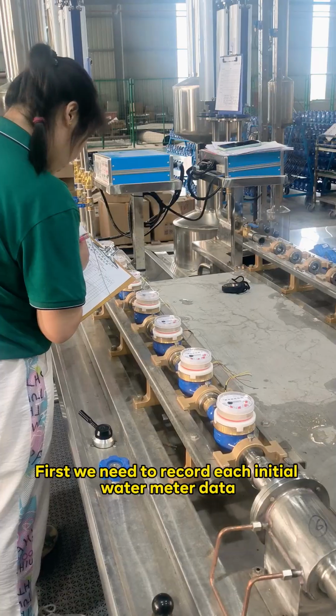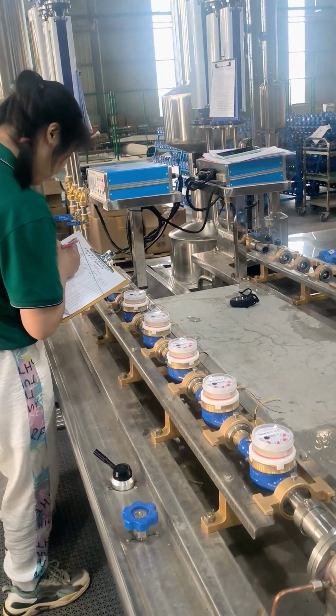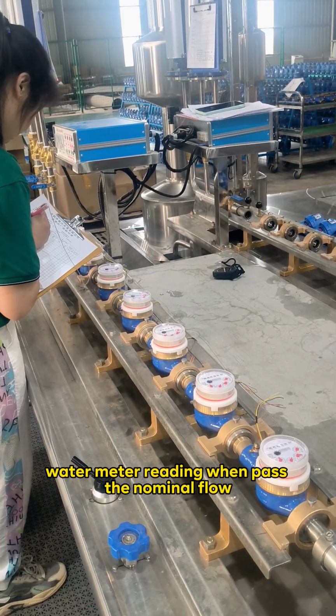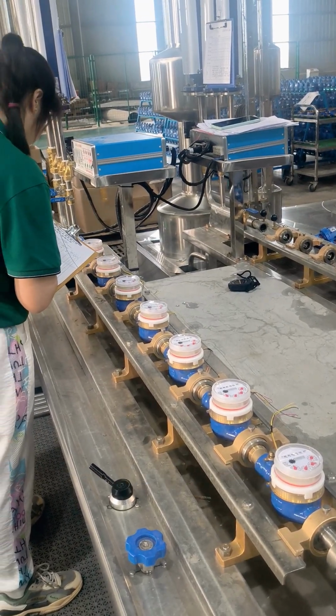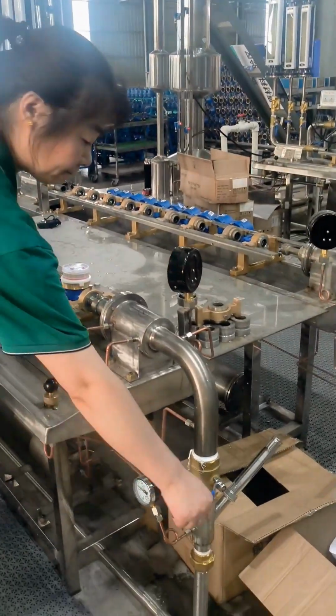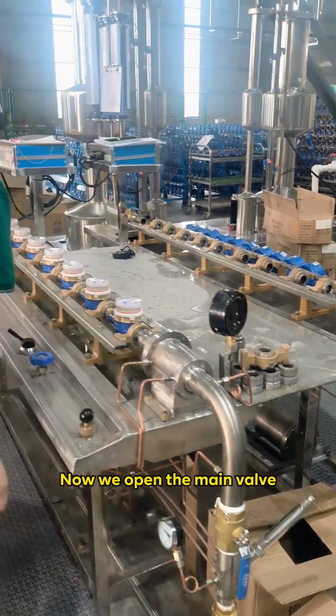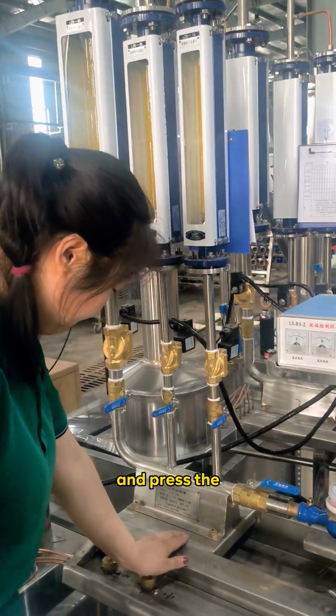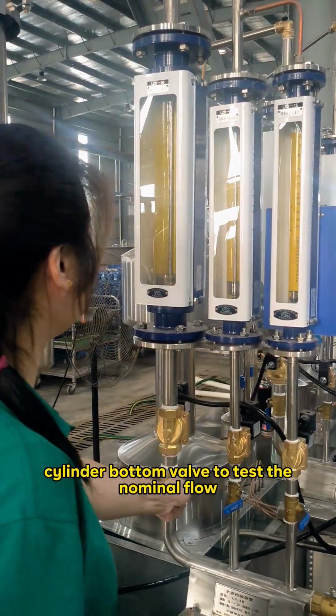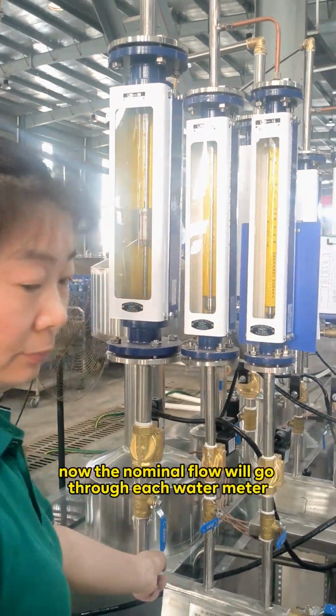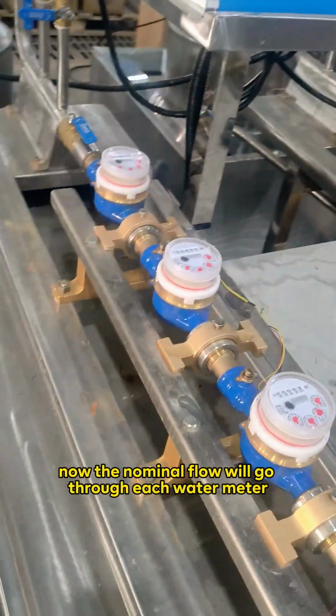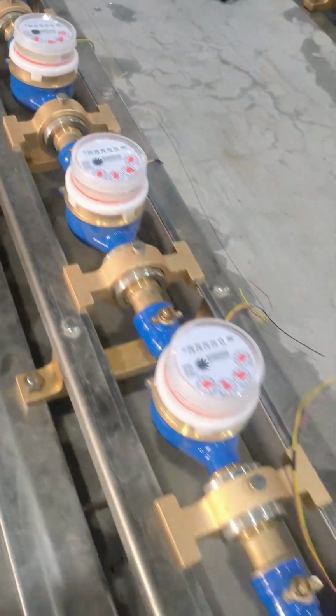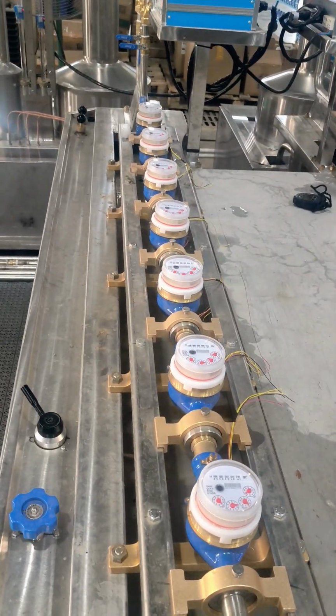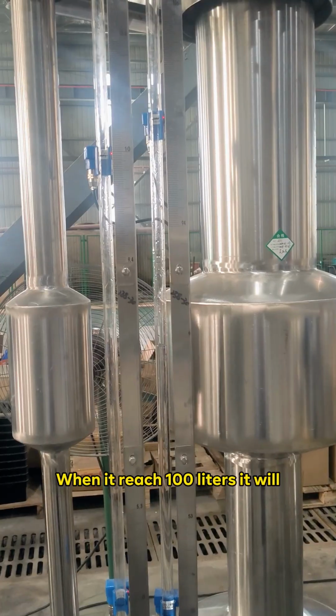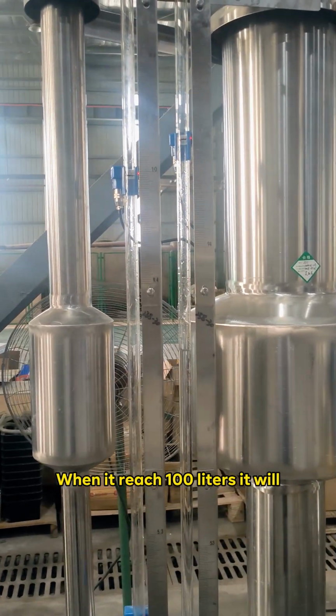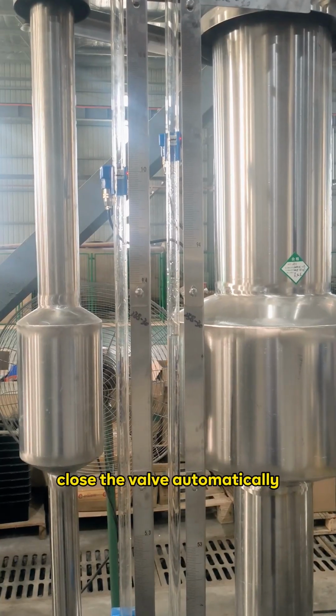First, we need to record each initial water meter data to compare with the data after the nominal flow. Now we open the main valve to test, and we press the cylinder bottom valve to test the nominal flow. Now the nominal flow will go through each water meter. When it reaches 100 liters, it will close the valve automatically.